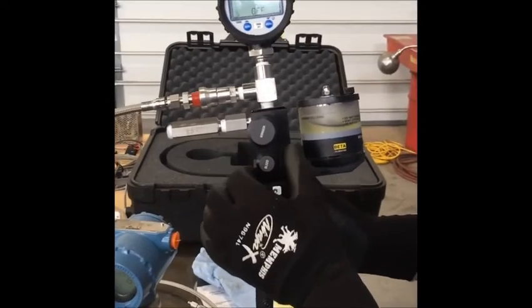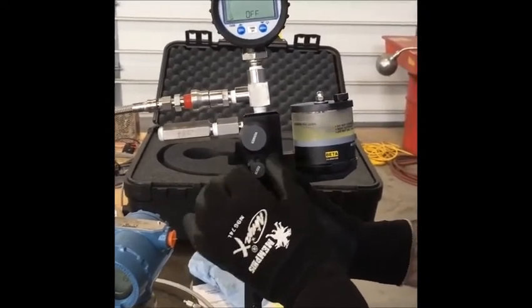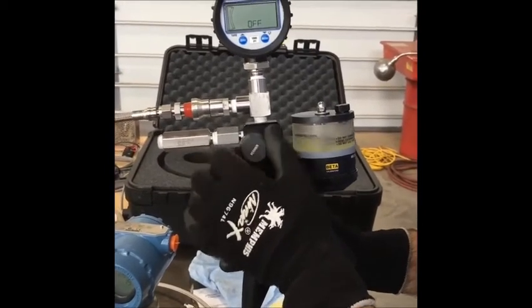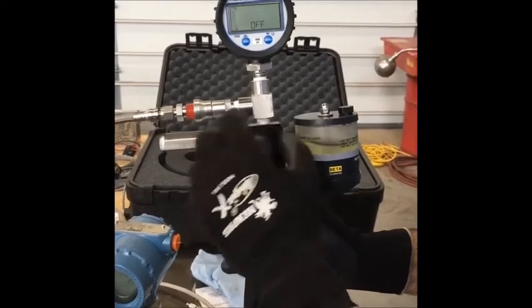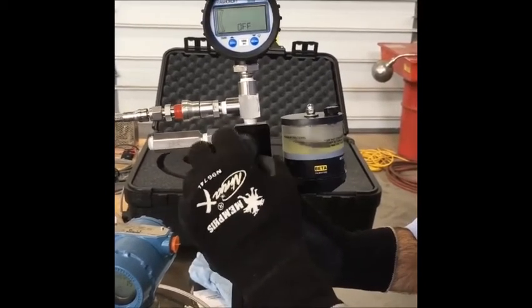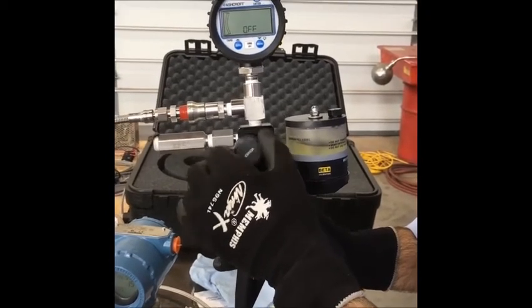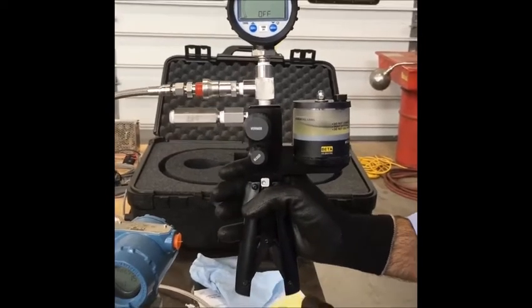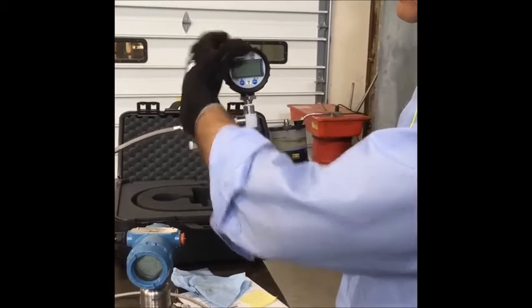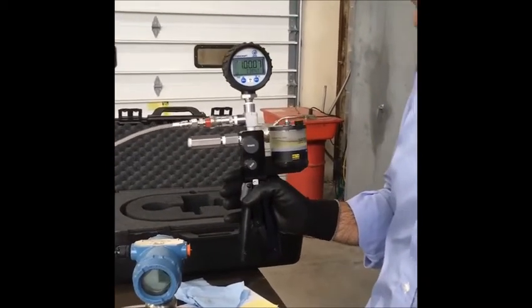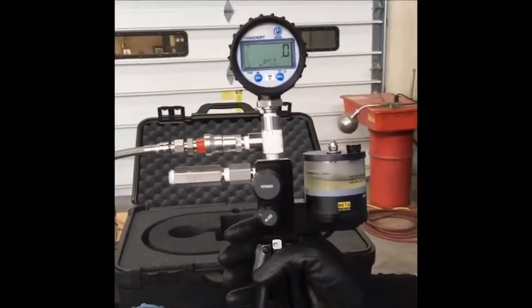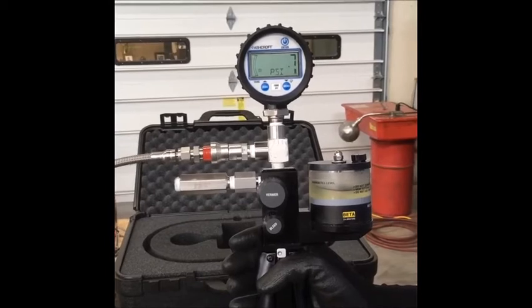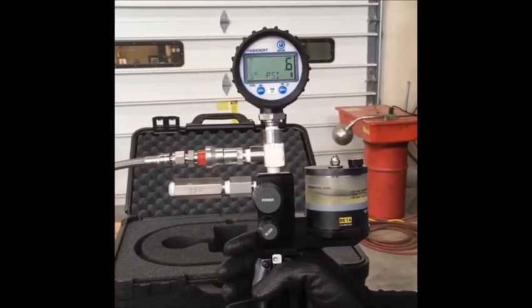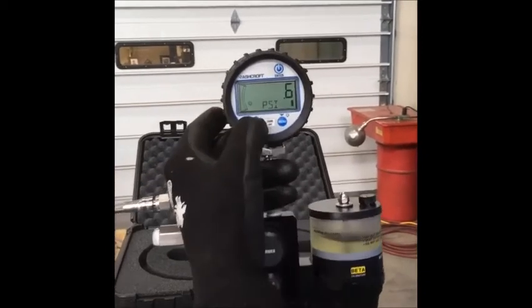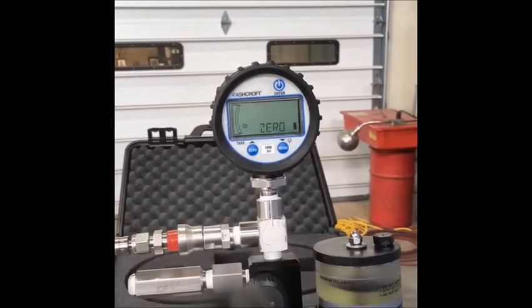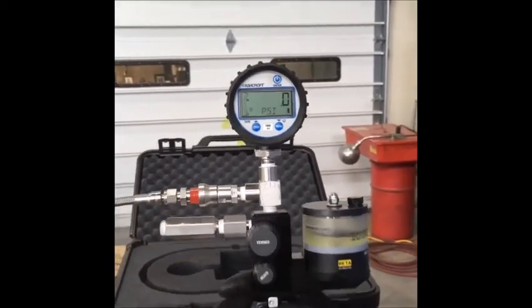Now the next thing we'd recommend is adjustment of these two devices. You've got a bleed valve that should be closed. So we'll close that all the way. And there's a vernier, which you might want to feel the full range on it. And you'd like to have it set roughly in the middle of its range. So we'll come out to there and we'll go in a few turns. We'll say 2 or 3 turns in should be fine for the initial setting. You need to turn the gauge on. So we press enter here. And we let the gauge come up to be powered on. It goes through its little test sequence. If it doesn't come up to 0, as you can see, mine's coming up to about 0.6 psi, and you can press the 0 on the gauge, and it will recalibrate for differences in atmospheric pressure.